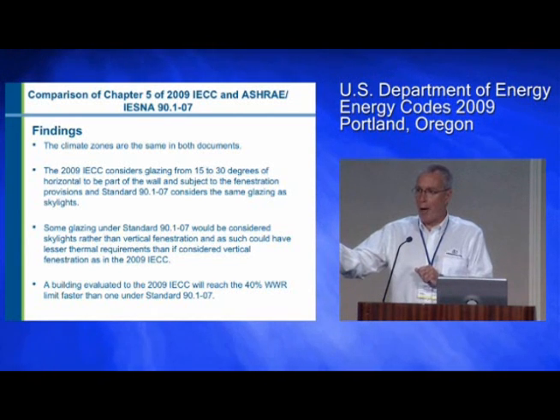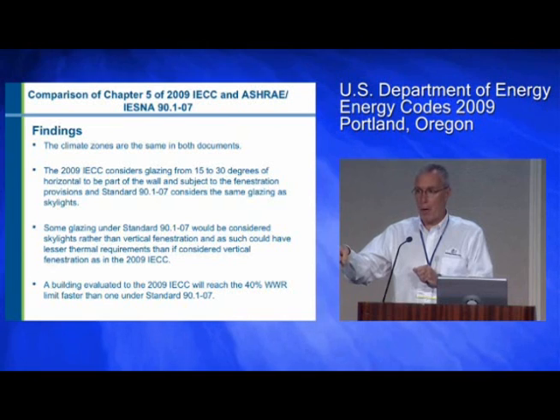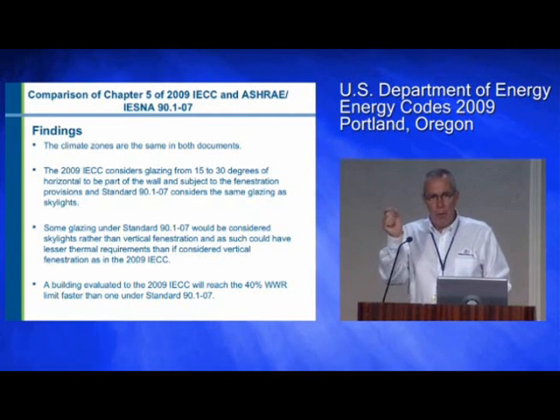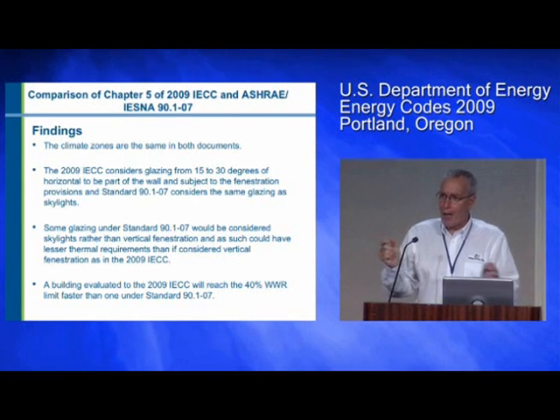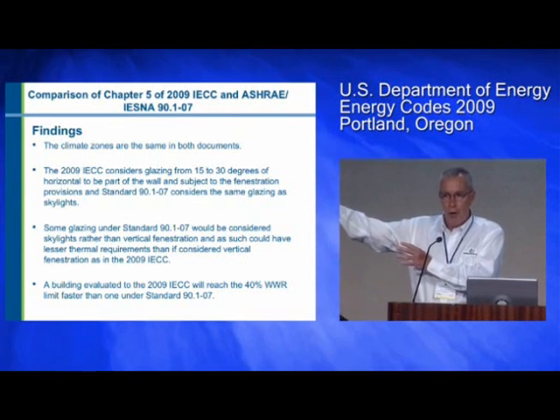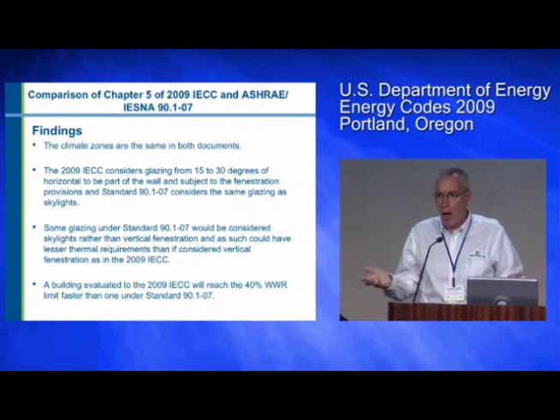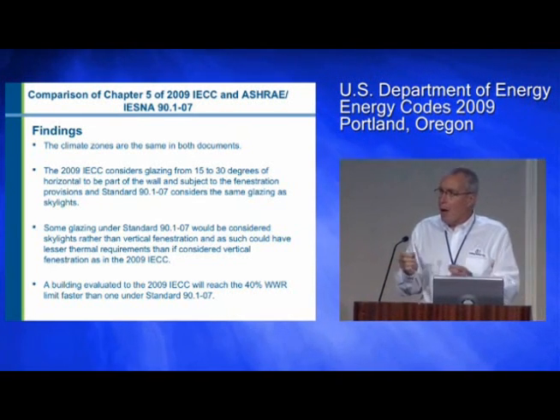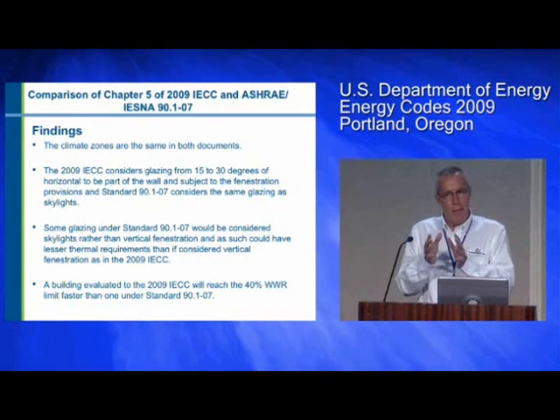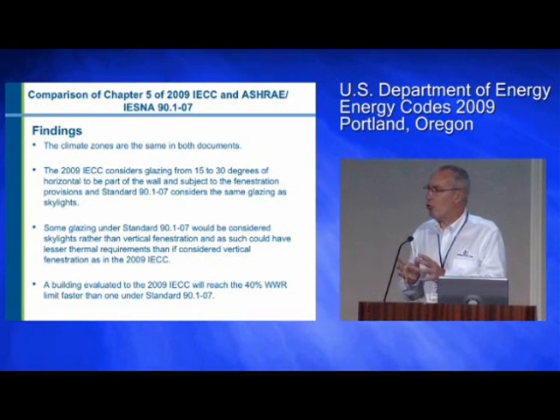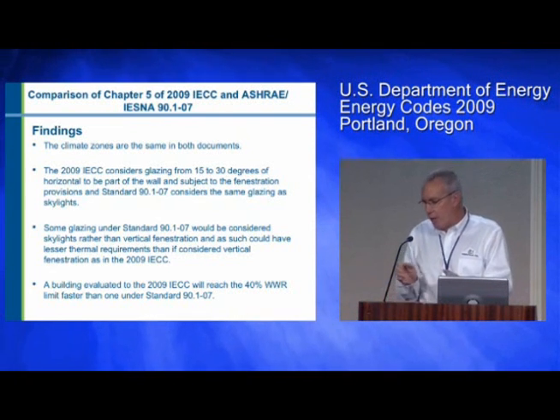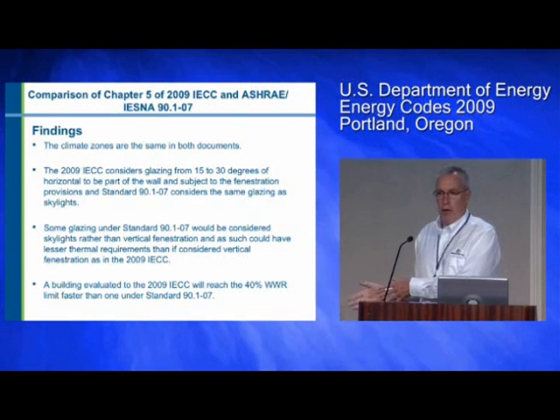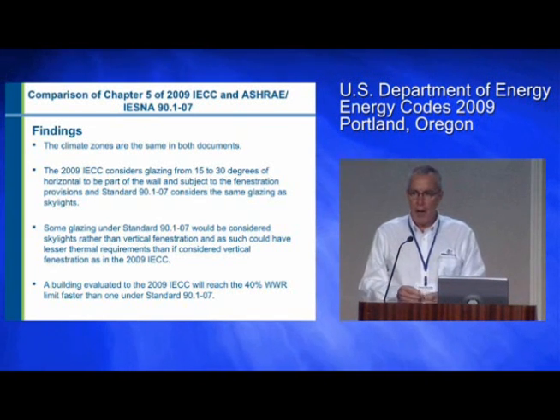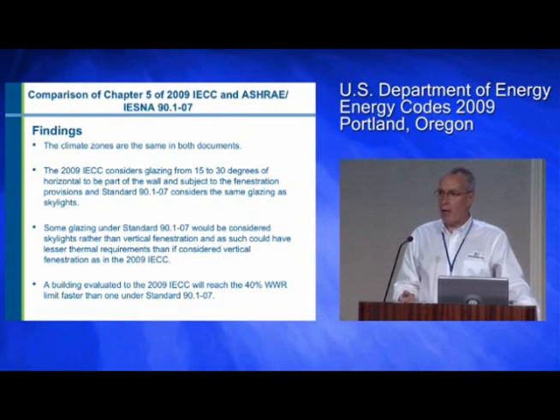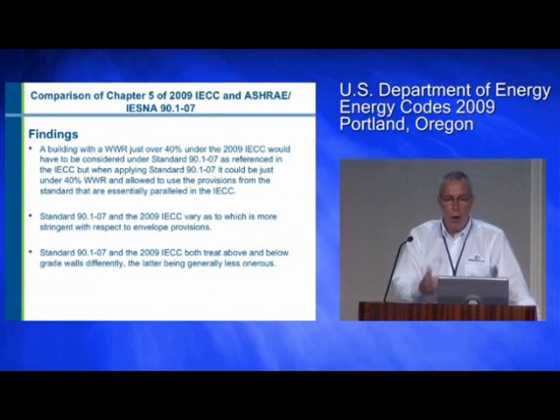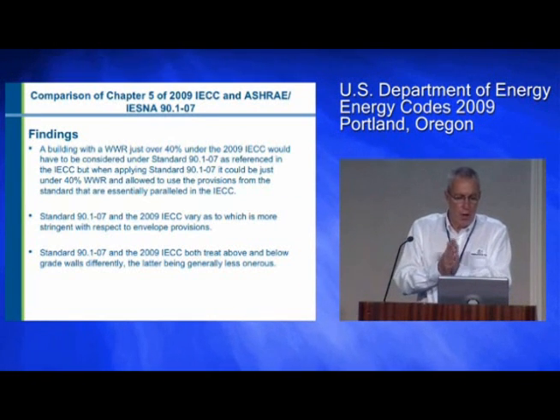And when I get to 90.1, it has a provision that if you're under 40%, you can do this alternative. So if I'm at 40.5% under the IECC, you see what I'm doing? I'm sent to another one. When I go to the other one, the way the metric is calculated, I'm at 39.5. And what's interesting about this is that it's not unusual for people to ask what the requirements are and jump into the technical provisions, and nobody reads the definitions. In many instances, how I define something can be just as important. So I just covered this 39, 41%, et cetera.